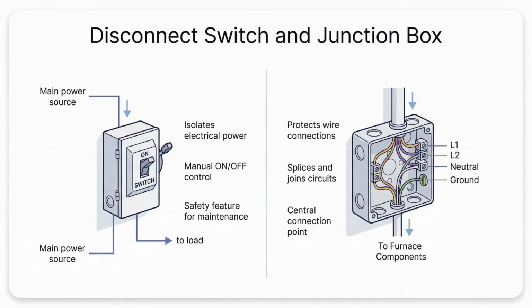Its job is to protect the wiring and equipment from dangerous overcurrents or short circuits. Thermal breakers use a bimetal strip that heats up and bends to break the circuit during a mild overload, while magnetic breakers trip instantly during a massive surge like a short circuit. The gas code requires a manual disconnect switch near the appliance so you can safely cut the power during servicing. Always test this with a meter.